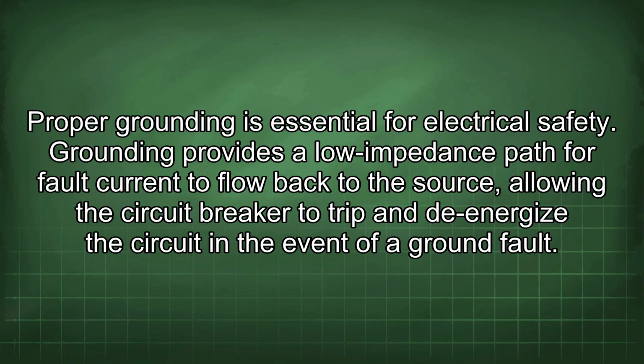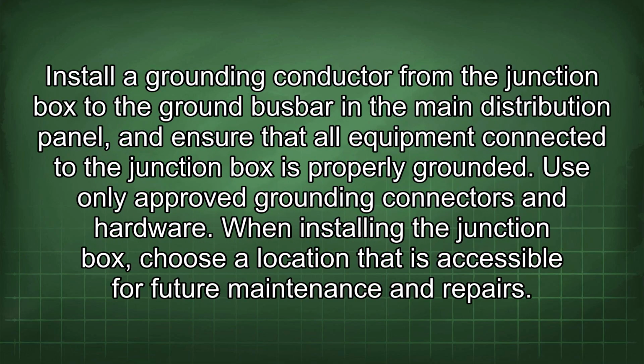Proper grounding is essential for electrical safety. Grounding provides a low impedance path for fault current to flow back to the source, allowing the circuit breaker to trip and de-energize the circuit in the event of a ground fault. Install a grounding conductor from the junction box to the ground busbar in the main distribution panel, and ensure that all equipment connected to the junction box is properly grounded. Use only approved grounding connectors and hardware.